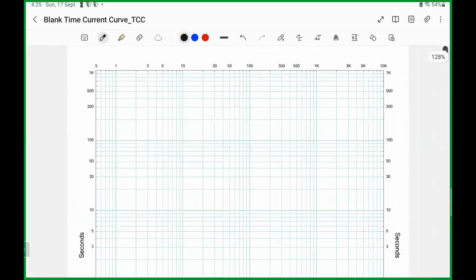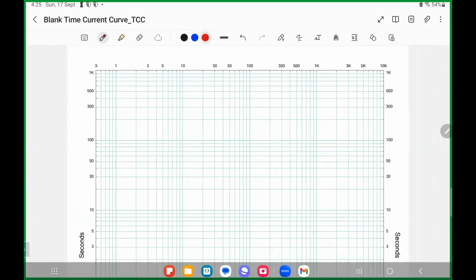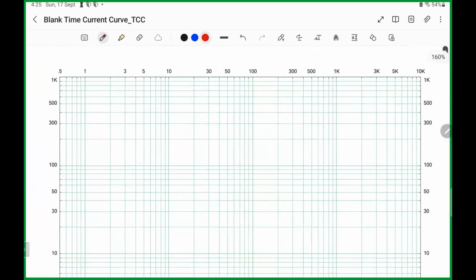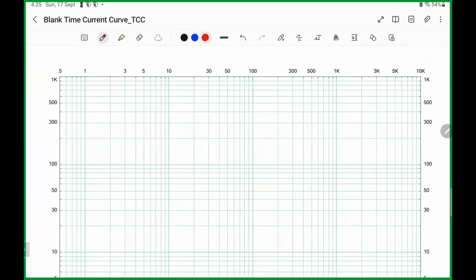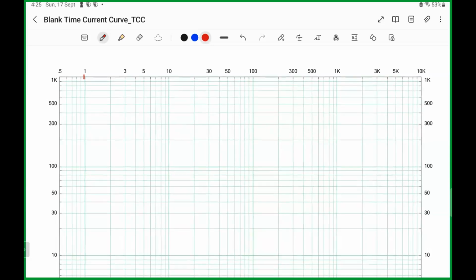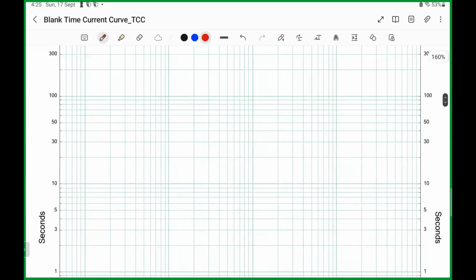Kung ito is 1 times 100, this is 100. So definitely yung full load motor mo nandito. Full load current ng motor mo before 1. Yan. So yan yung FLA mo. That is a continuous operational current of your 75 horsepower. Now let's find the LRA symmetrical at 5 seconds. So hanapin natin yung 5 seconds kasi yun daw yung accelerating time.